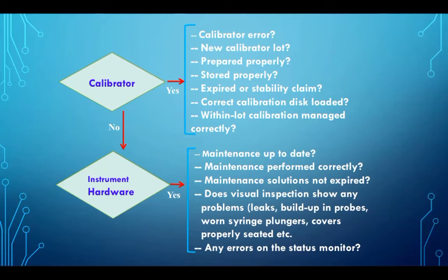What you can do, you develop a system in your laboratory, develop a schedule, and you say we will run this calibrator as a sample, and we will see what is the value written on that calibrator and how much we are getting. If you are getting a significantly lower or higher value, there is a problem in the accuracy.